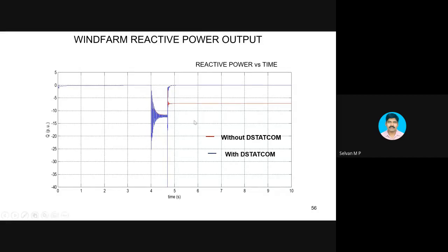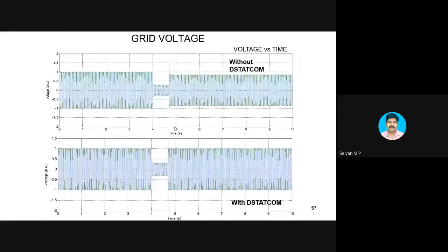So this reduction in reactive power demand after clearing the fault, as well as the machine being connected to the system without any disturbance, will be achieved with the help of the STATCOM. Of course, there is an oscillation in real power, which should be reduced with sophisticated control. We have to reduce the oscillations in the real power as well as in the reactive power.